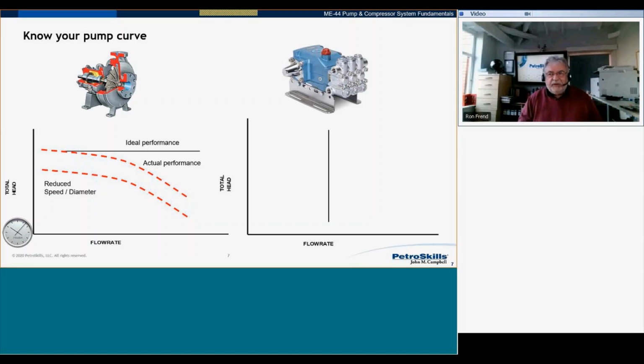So now we can say if we change the flow rate, we can change the total head that the pump develops. That's going to be useful, and that's going to be something we're going to look at. But if you look at the shape of that curve, keep that in mind, and then look over to the right. And what we see there is a positive displacement pump. Now, I don't care if it's a recip or a rotary, it's a positive displacement pump.